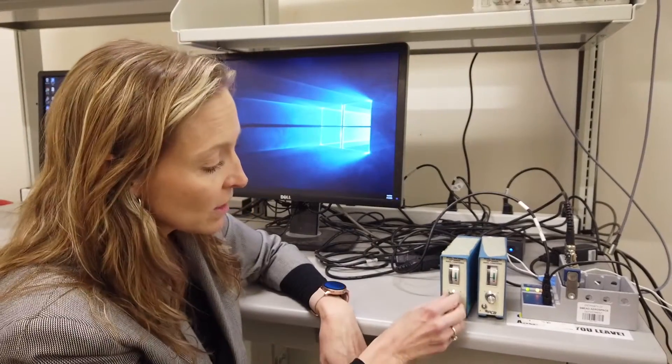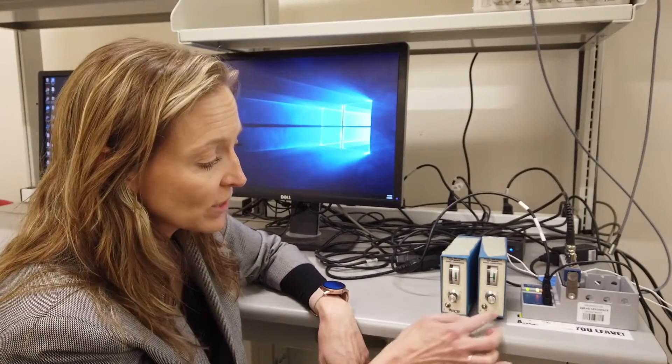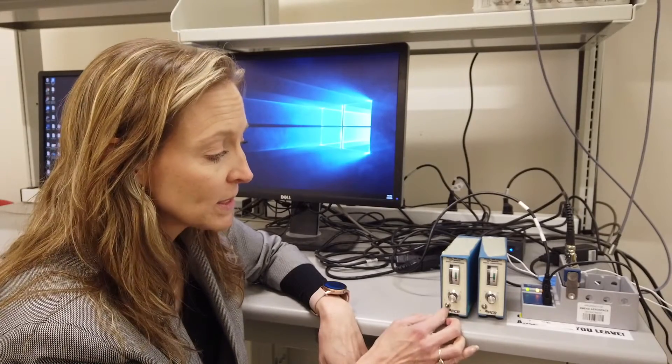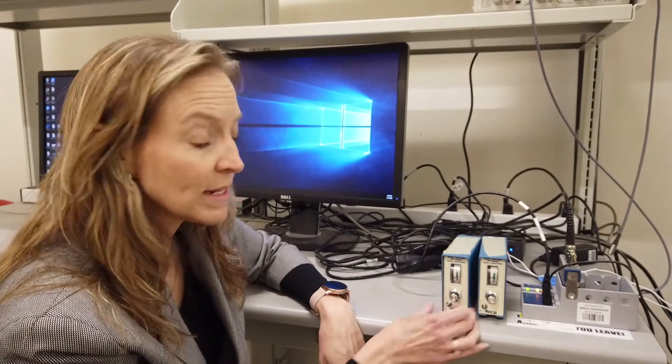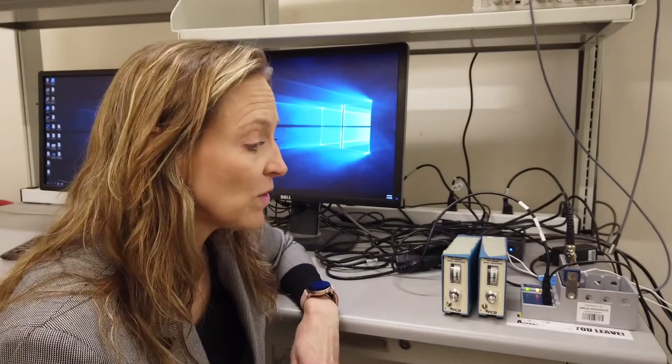These knobs on the front are your zeroing knobs and you will zero each of the sensors independently. You will do that as a very important part of your checklist and coordination between the indoor test control room people in your group and the people who are doing the launching at the test stand next door.